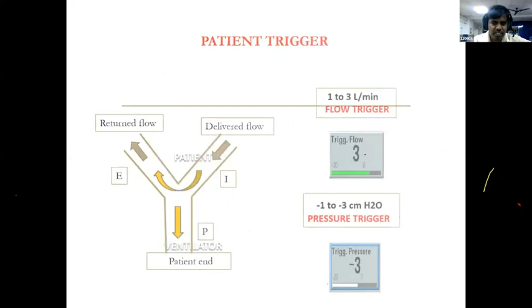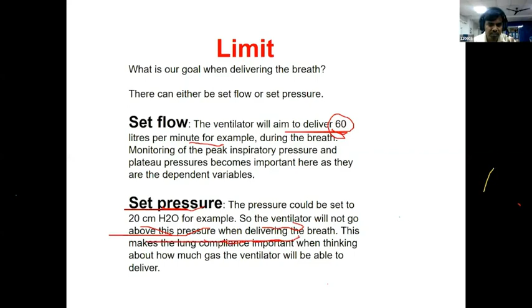Yes. So you see here, trigger. I discussed what is limit. Your flow limit should not exceed 60 liters per minute. This is also very important, which will be set in the ventilator. And the pressure, which we discussed, the peak pressure, usually 20 centimeters is more than enough, for example. So the ventilator will not go above this pressure when delivering the breath. So flow limit is set flow and pressure, and then cycle.